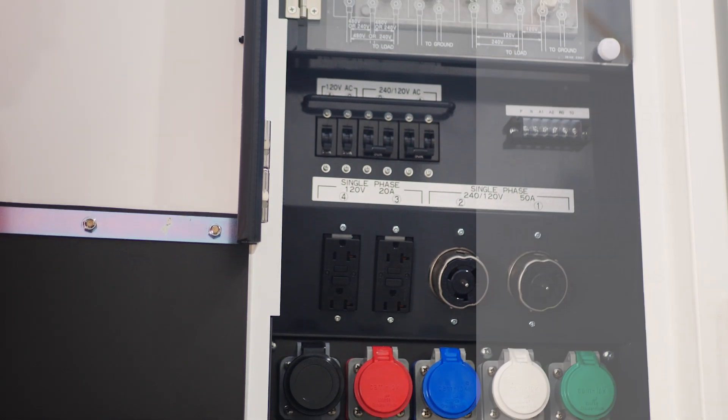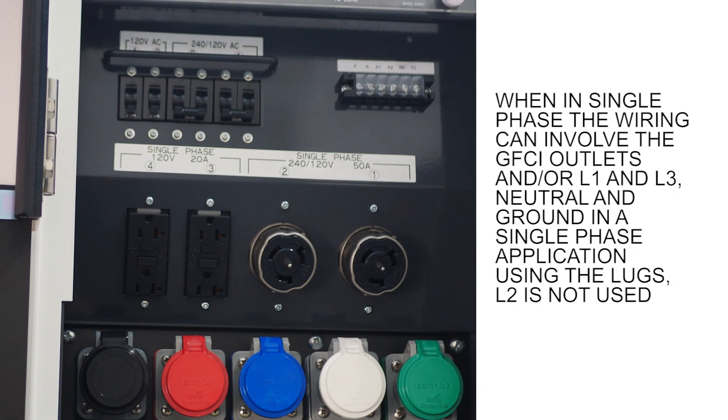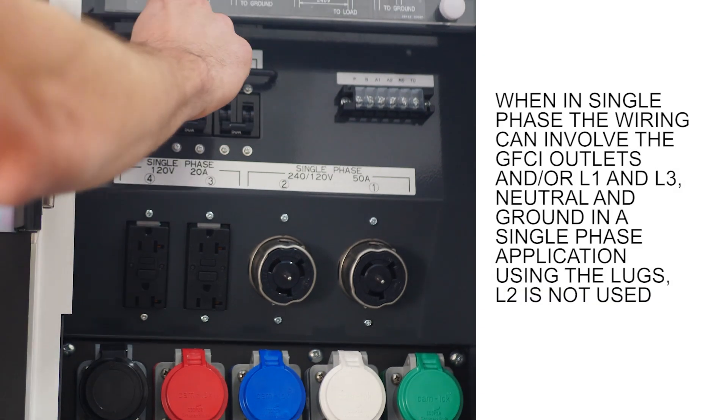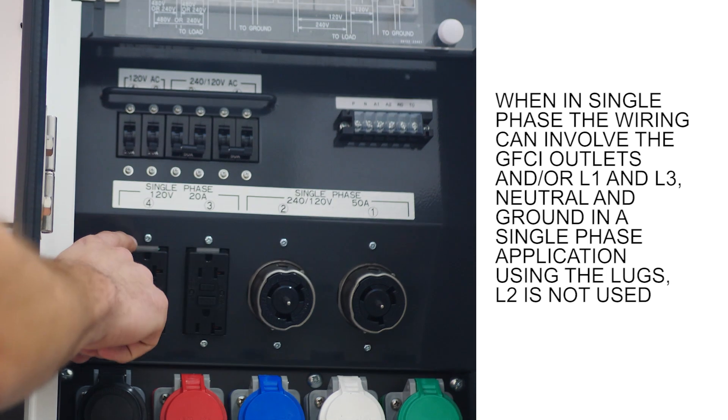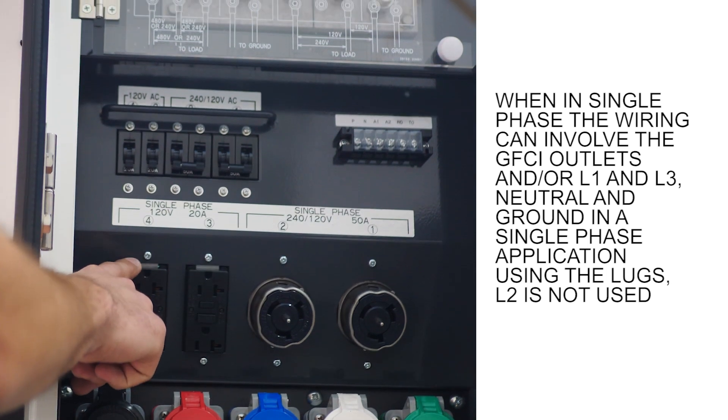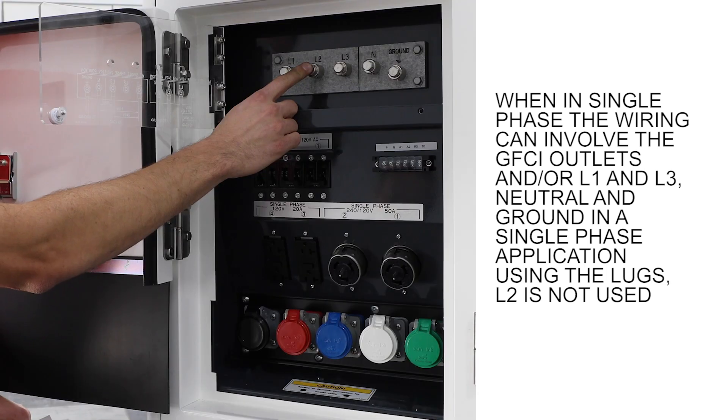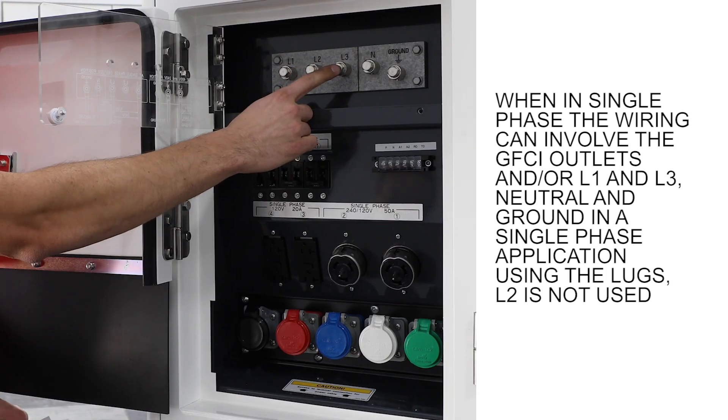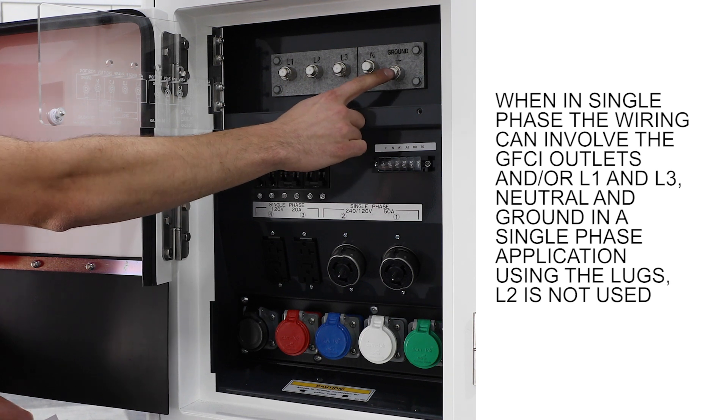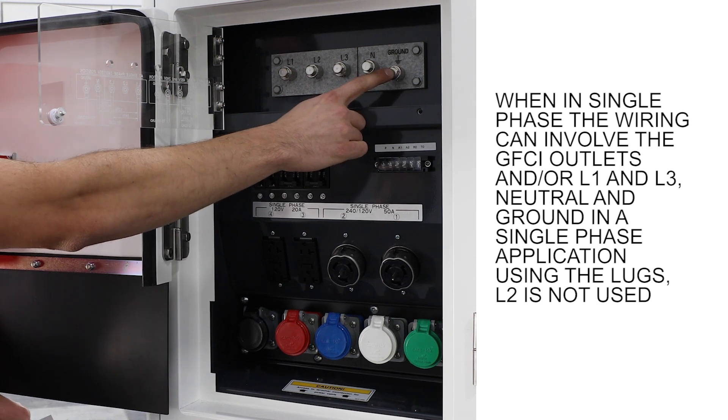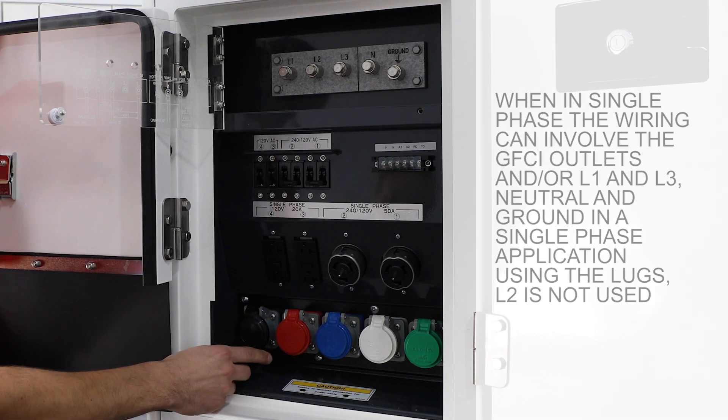When in single phase, the wiring can involve the GFCI outlets, the 50 amp twist lock, or L1 and L3 neutral and ground in single phase applications using the lugs. L2 is not used.